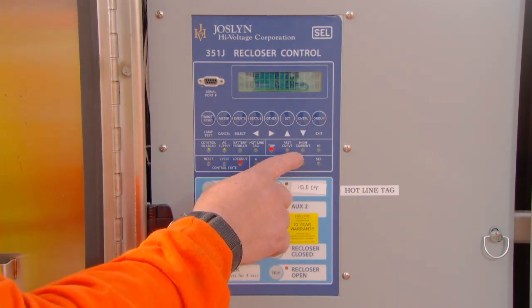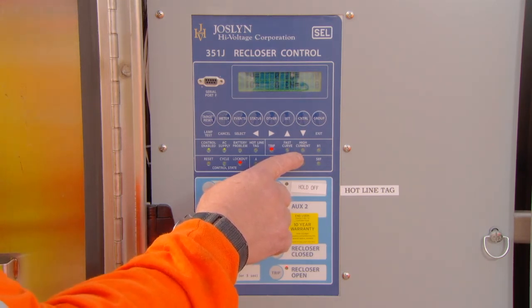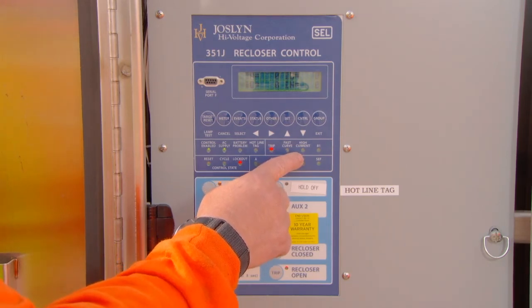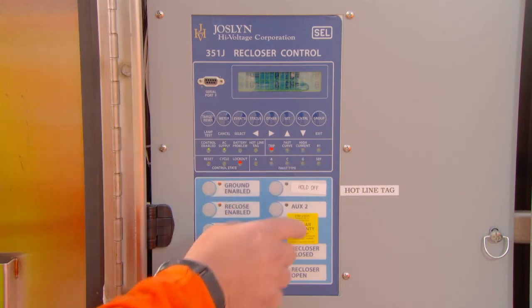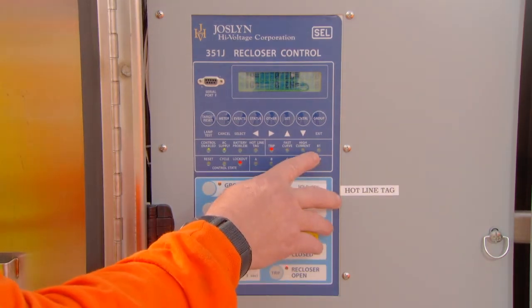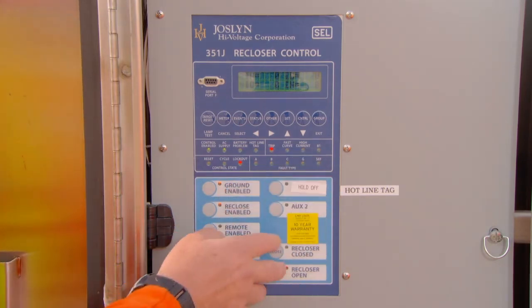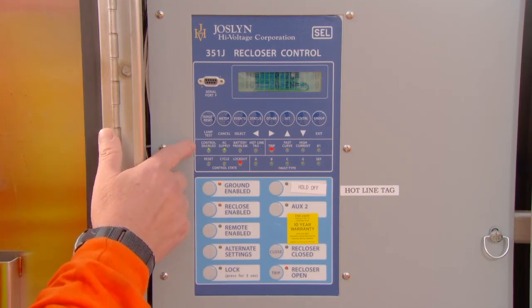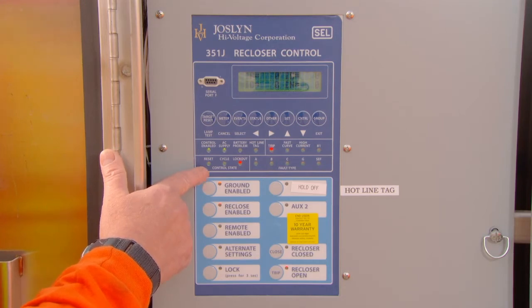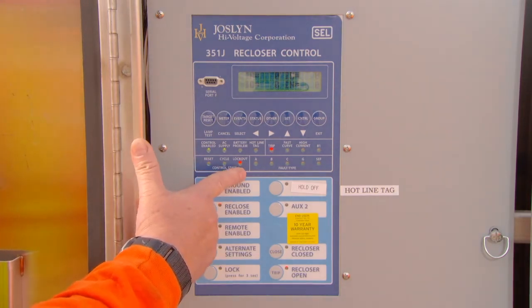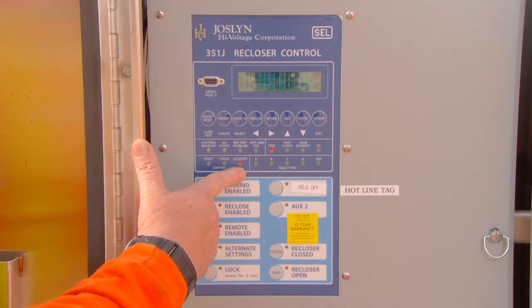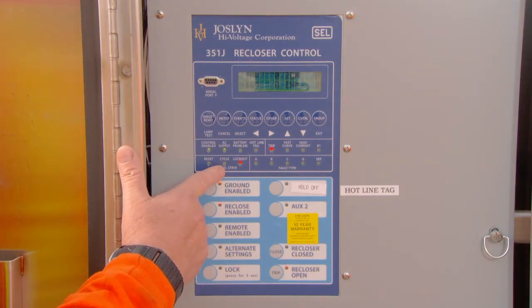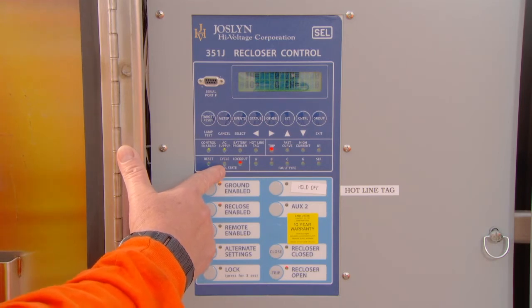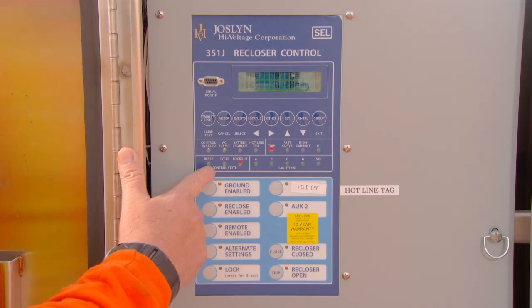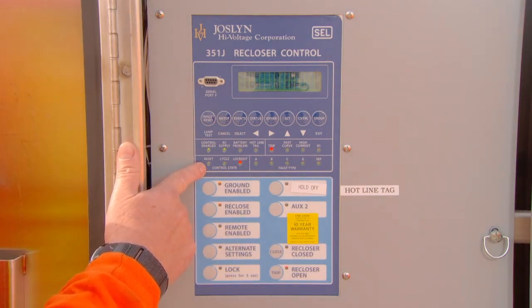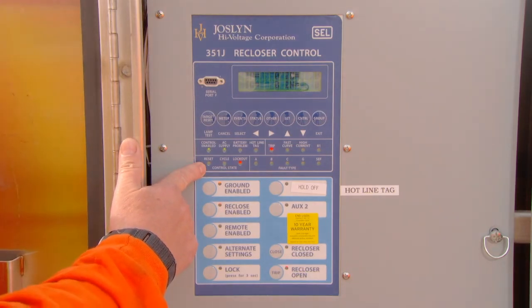If the high current setting was applied to the control, this indicator would turn red if it tripped on a high current fault. The 81 indicator is not used in any of these controls. Moving down to the next level of indicator LEDs, we have Reset, Cycle, and Lockout. In the lockout state, all three phases are open and locked out, while in the cycle state, waiting for the next operation, the cycle light would also be on. Moving on to the Reset indicator LED, when the recloser has closed, it will change to the reset state after the programmed time of approximately 10 seconds.